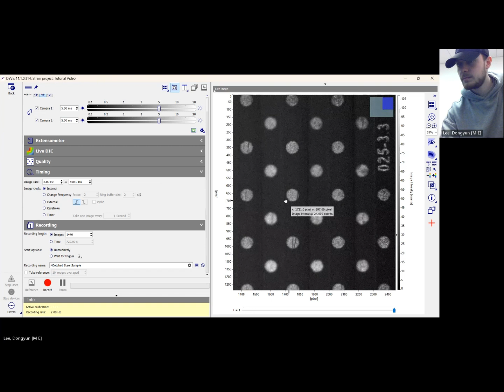Once you have the cameras aligned, it's best to look closer. You can zoom in here and see how the camera is looking. From this point, zooming in and out using the focus, we can see that our camera is pretty good. So now we will switch to the second camera and do the same thing. Like I said, same thing here. We're going to zoom in on the image. Best to see how our pixels are looking, and see if adjustments are needed. It's really good with the calibration plate because you can see the numbers here as a good indicator of how well your cameras are focused.